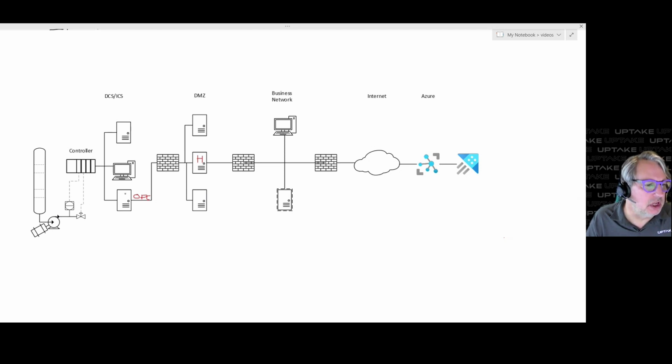Now, in addition to those signals, calculations carried out in the control system can also detect alarms or other sorts of events. This data is structurally different from the data in a historian, and so it tends to live in an alarm and event database, often abbreviated as A&E. This data is quite different from the historian data in terms of the data structures and how it's queried. So it tends to live in a different system.